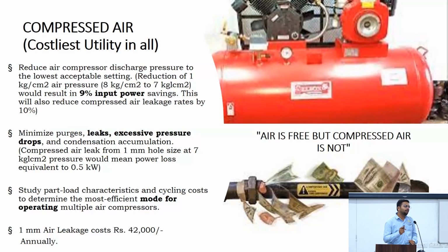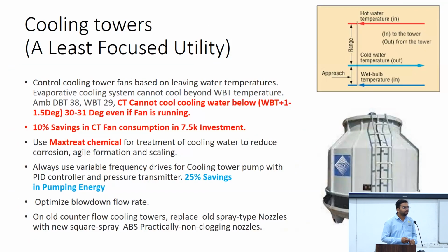So every small air leakage also needs to be addressed. Also, like the steam system, compressed air systems have leakage due to moisture in the system, because moisture is the reason for water accumulation in the weakest part of our distribution system, and that will cause leakage. So we identify that leakage point, but we know that a leakage will always be there. We need to remove the root cause of the leakage, why the leakage is happening. We remove the leakage by introducing a dryer in the compressed air system. So we optimize the compressed air with the dryer application also.